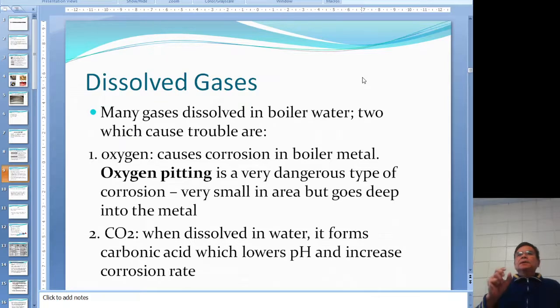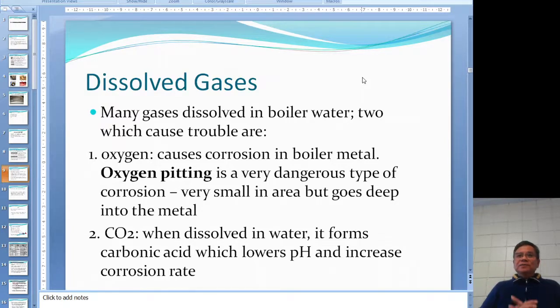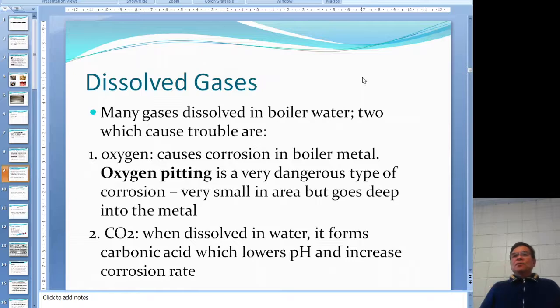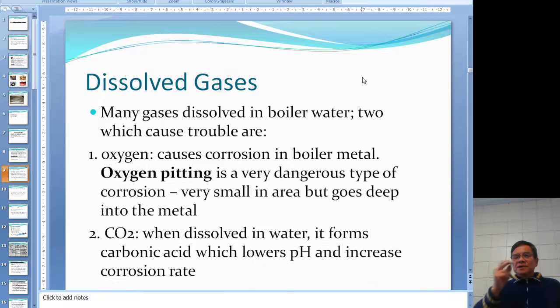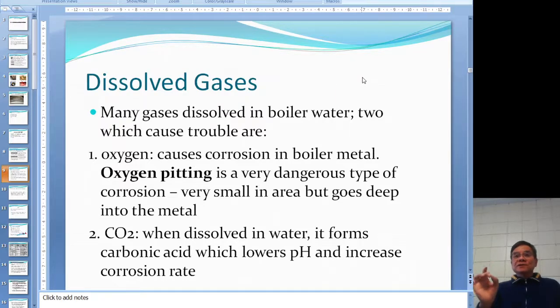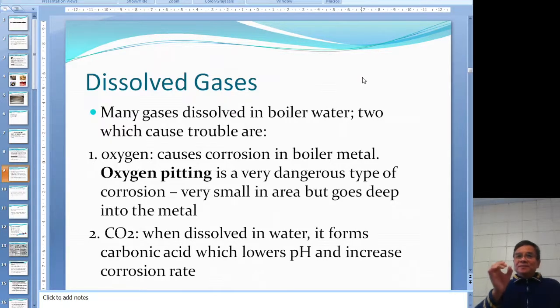For dissolved gases, we don't worry about nitrogen, but we do care about two: oxygen and CO2. Oxygen causes corrosion because the boiler is made of steel — iron — and the result is FeO and Fe2O3. If there is no oxygen, you cannot form rust. So we must get rid of oxygen.